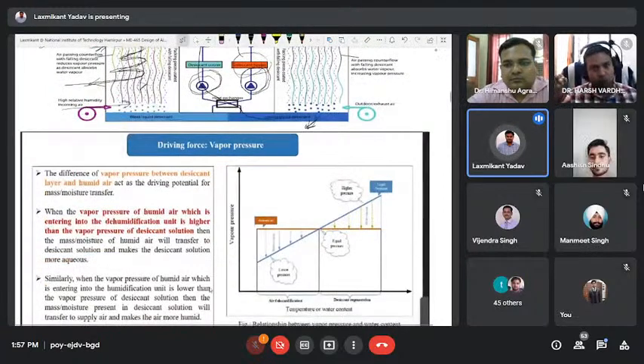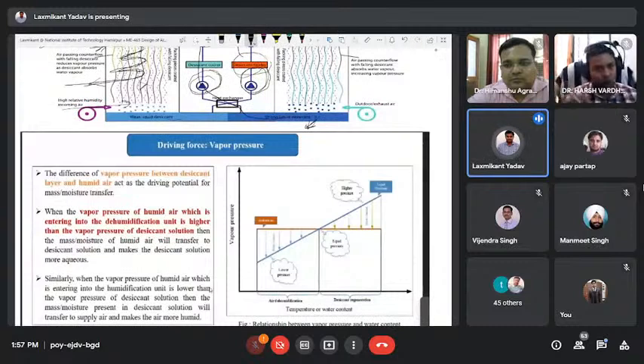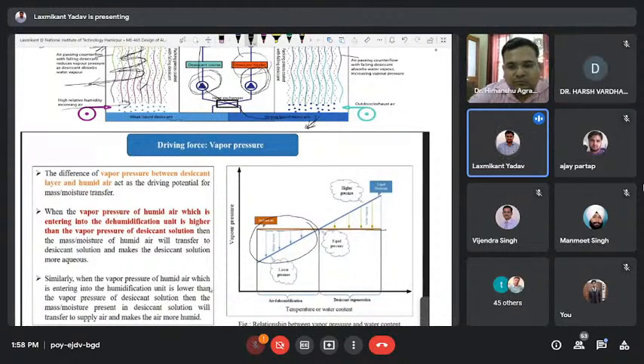Okay, so this is the vapor pressure diagram. During the absorption part, the ambient vapor pressure is constant. During the absorption, the vapor pressure of the ambient air is higher than the vapor pressure of the liquid solution. However, in the case of regeneration, the vapor pressure of the liquid solution is higher because of heating. As we heat the solution, the vapor pressure increases, and that vapor pressure is higher than the ambient vapor pressure. So there will be regeneration. Clear?